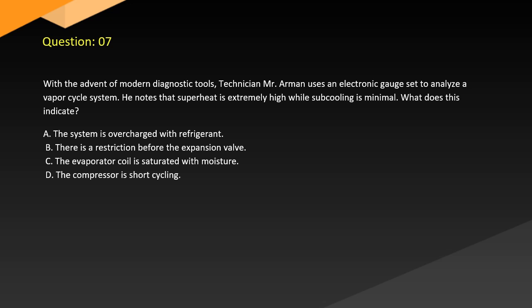Question 7. With the advent of modern diagnostic tools, technician Mr. Arman uses an electronic gauge set to analyze a vapor cycle system. He notes that superheat is extremely high while subcooling is minimal. What does this indicate? A. The system is overcharged with refrigerant. B. There is a restriction before the expansion valve. C. The evaporator coil is saturated with moisture. D. The compressor is short cycling.